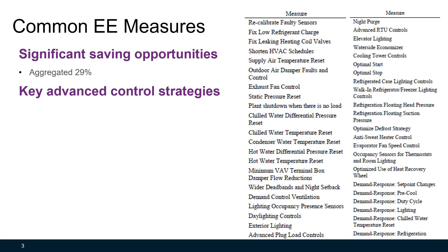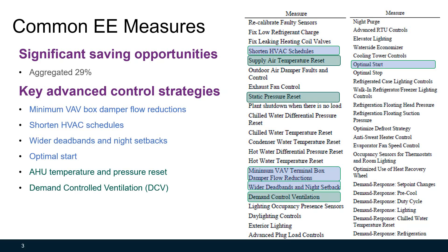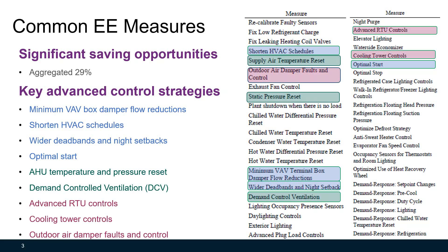Here's the list of advanced control strategies and common energy efficiency measures. 29% of savings can be achieved by these advanced control strategies. One group includes minimum VAV box damper flow reductions, shortened HVAC schedules, wider dead bands and night setbacks, and optimal start. Another group includes AHU temperature and pressure reset and demand controlled ventilation. A third group includes advanced rooftop unit controls, cooling tower controls, and outdoor air damper faults and control.